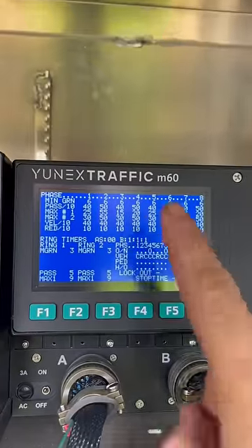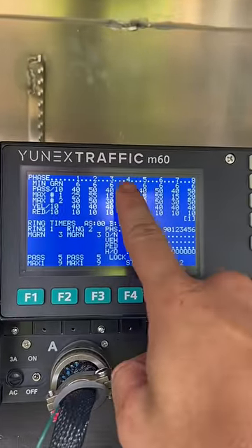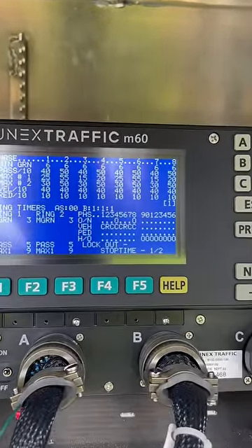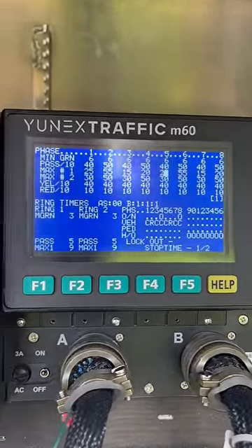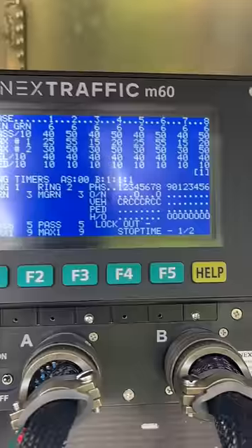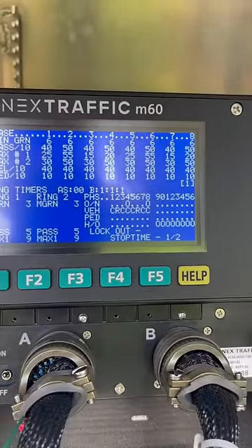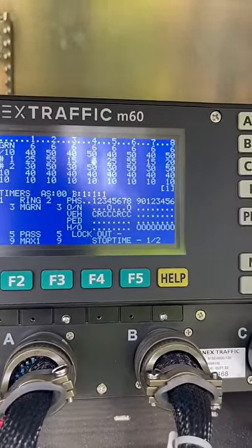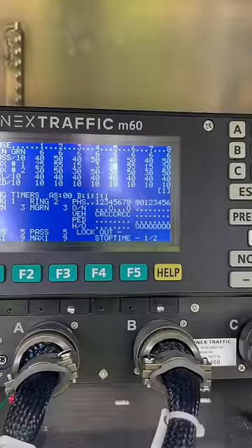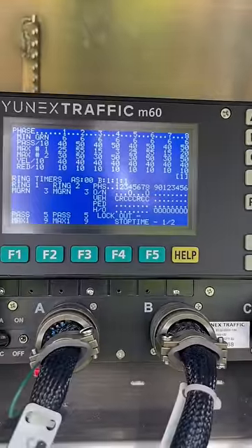Let me show you. Say that that was phase four of that intersection. If I wanted to change the times, I can go down to max one and over to phase four and say I want to put 30 seconds in. I accidentally just hit three and then I don't check my work and I just walk away from this intersection. So there you go — now you know how to change the times at an intersection and also why that light may have only been three seconds.